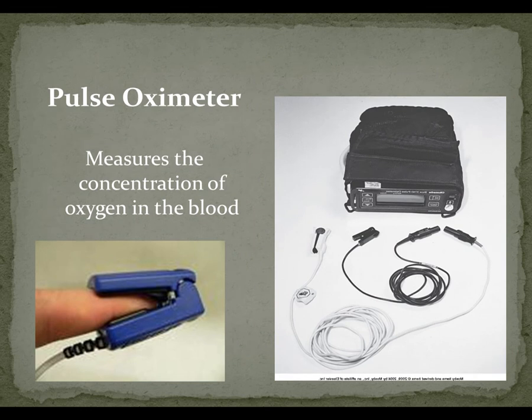A pulse oximeter is a piece of equipment that you may need to use if you sedate a patient or if you're involved with any kind of interventional procedures. A photosensitive cell inside the oximeter detects the difference between oxygenated and deoxygenated hemoglobin. It works by passing a beam of red and infrared light through a pulsating capillary bed.